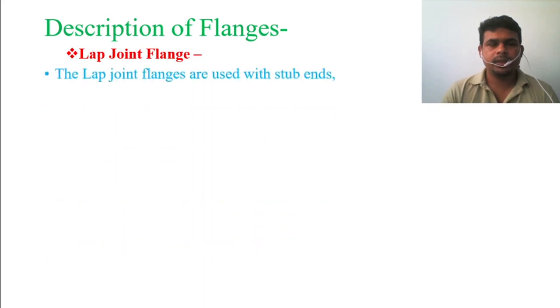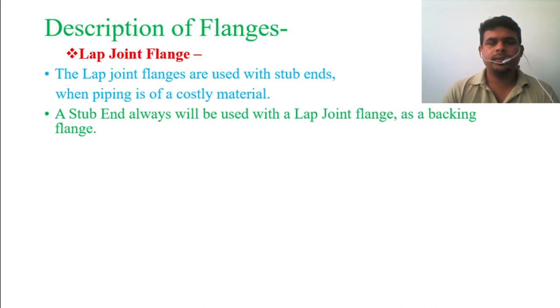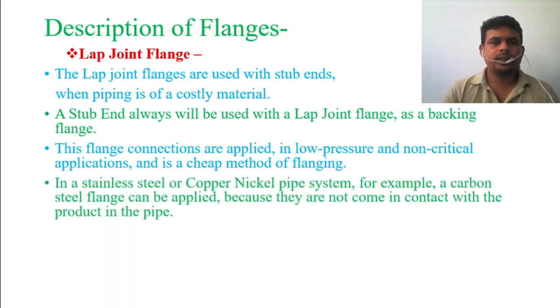Lap joint flanges are used with a stub end when the piping is of a costly material. If the pipe is a costly material, you can use the lap joint type of flange — the flange itself may be a cheaper material while the actual pipe material is very costly. The stub end is always used with the lap joint flange as a backing flange. This flange connection is applied in low pressure and non-critical applications, and it is considered a cheap method of flanging.